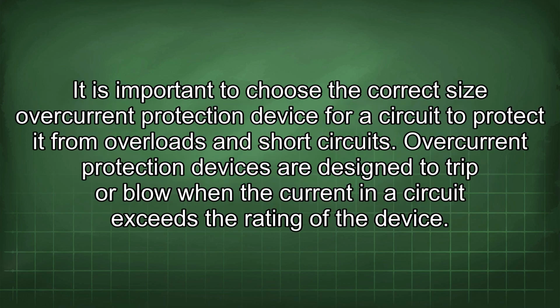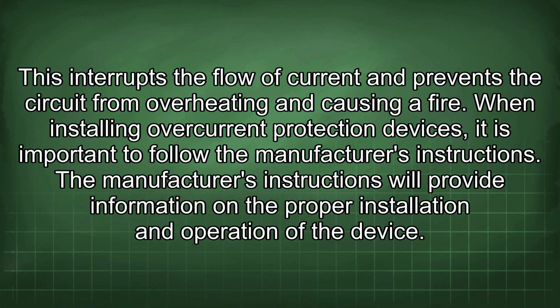It is important to choose the correct size overcurrent protection device for a circuit to protect it from overloads and short circuits. Overcurrent protection devices are designed to trip or blow when the current in a circuit exceeds the rating of the device. This interrupts the flow of current and prevents the circuit from overheating and causing a fire.